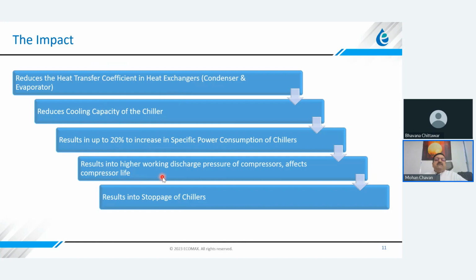Also, the compressors of the chillers need to work at higher discharge pressures. And that's where it affects the compressor life as well. And then the regular practice is to stop the chillers periodically. Could be 1 month, could be 3 months, could be 6 months, 1 year, depending on the scale forming tendency of the water at various industries.